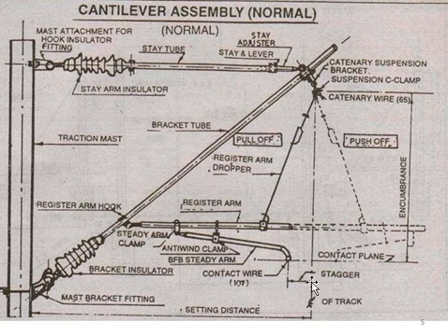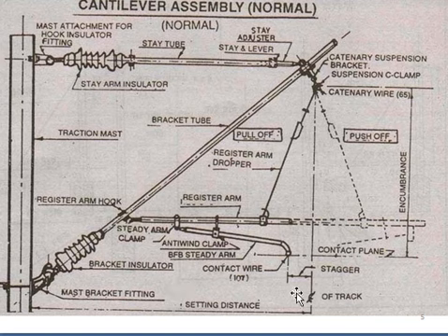Only staggering is done in the contact wire's case. Sometimes it will be inside, sometimes it will be outside. Here it is staggering. I'm again explaining staggering. If this contact wire is inside, it is an inside staggering, negative staggering, and if it is going outside, it will be positive staggering. And this is center line of track, and this distance is also called implantation, from face of the mast to center line of track.